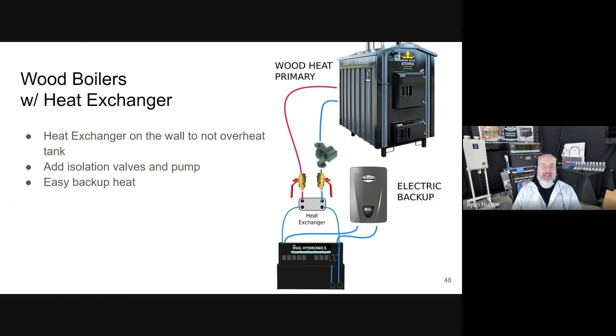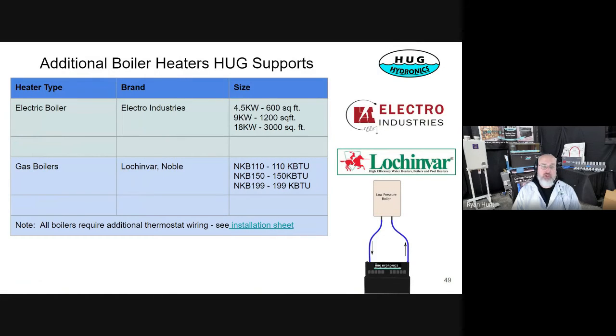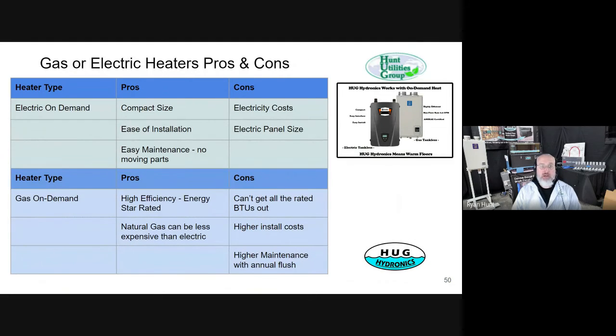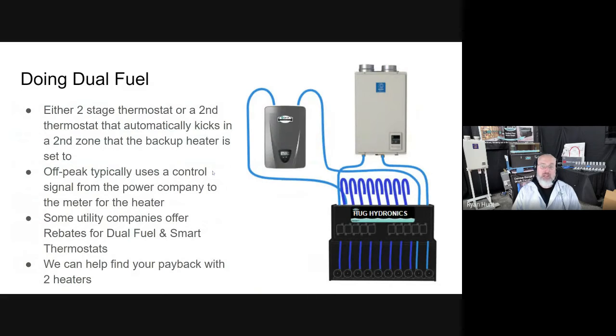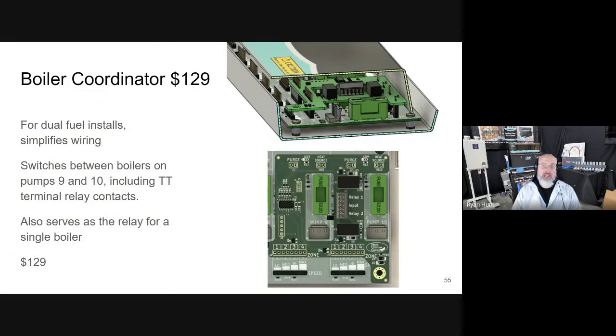And it's real easy to add an electric backup. There's other boilers we sell from Lochinvar and Electro Industries. They're the most common. The gas or electric pros are the gas is a little cheaper, especially for natural gas, a little cheaper for propane, but electric, it's really easy to install. The boiler itself is cheaper. The hardware for the gas is more expensive, but you can go dual fuel and take advantage of them that way. To do that, we have this handy dandy add-on board that'll control 2 different boilers and switch from one source to the other.